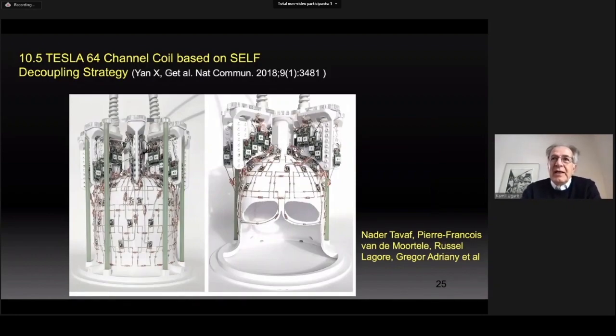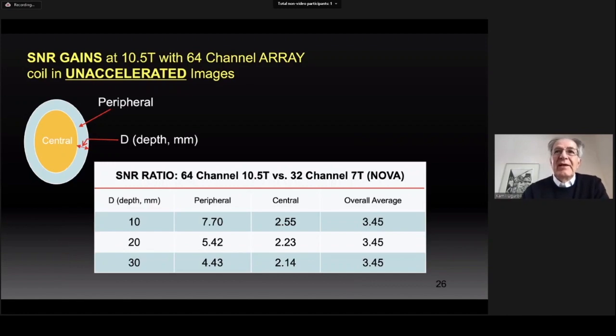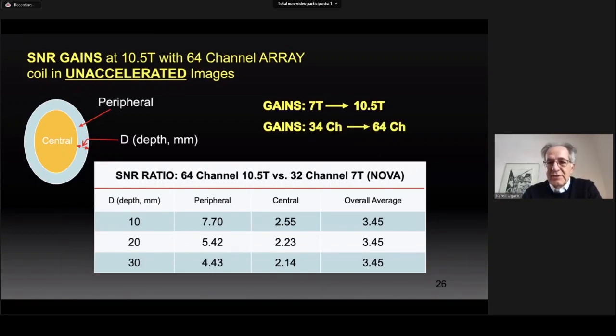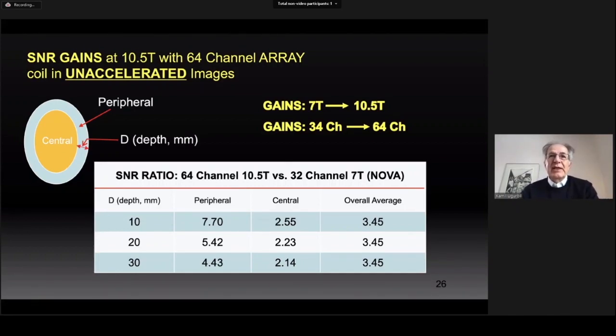Within this project we have gotten 10.5 tesla working, and this is our most recent 10.5 tesla human head coil, which has 64 channels. Here is an SNR comparison at 10.5 tesla with our 64-channel coil versus 7 tesla with the commercial 32-channel RF coil — the one used for all the experiments presented so far. Note that in this comparison we have gains due to the magnetic field going from 7T to 10.5T as well as gains from the channel count increase from 32 to 64 channels.